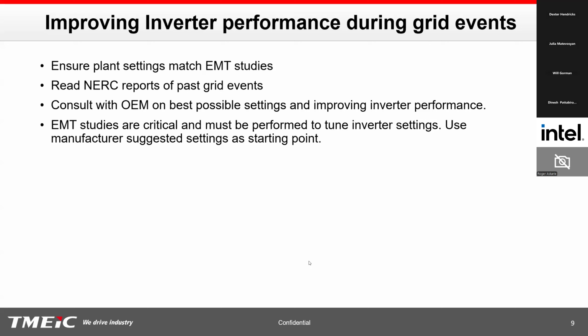The other thing to do would be to consult the OEM on the best possible settings, to confirm with the OEM how each protection setting works in the inverter, and make sure their recommendations are taken into effect when tuning the model performance for the plant as well. It is also important to study past grid events and consult with the appropriate OEM on what model settings can improve inverter performance, and whether the OEM has a mitigation strategy for events that were experienced in the past. So these are just a few suggestions that don't relate to 2800, but are very key to how inverters perform in the field.